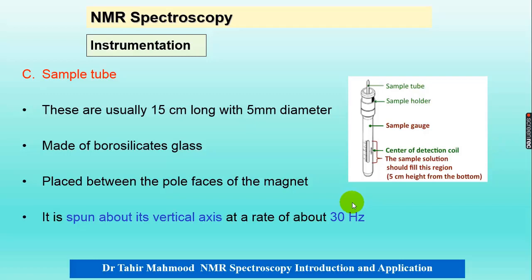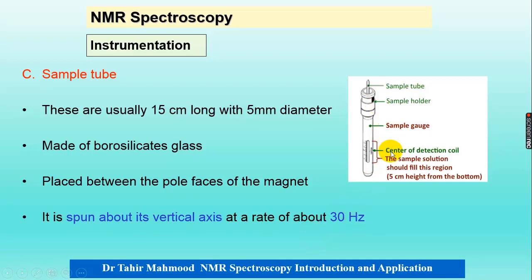The sample tube: in NMR spectroscopy, we mostly use the solution form or liquid sample. For sample preparation, we use solvents that are proton-free or contain deuterated isotopes of hydrogen. The tube is normally 15 centimeters long and 5 millimeters in diameter, made of borosilicate glass, placed between the poles of the magnet, and spun about its vertical axis at 30 hertz per second. The sample solution should be set in the region 5 centimeters high from the bottom.